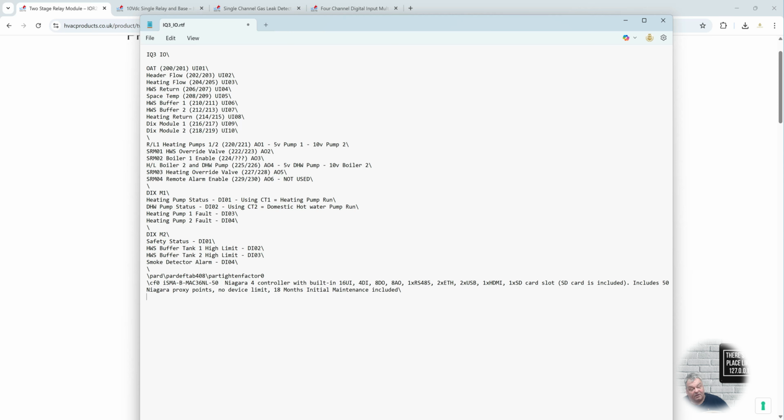Personally, if I'm using a MAC36, which I am, I would prefer to wire all these 4 safeties directly into the MAC36 rather than using another module that can go faulty. But that's just me.